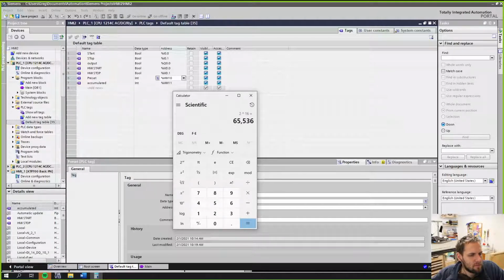Because that doesn't count 0. Right, but this is saying only can go up to 32,000 and only down to negative 32,000, yet this is saying 65. Oh, because it's split in half to have negatives. Excellent. It's split in half, so that way we can go both from negative 32,000 to positive 32,000. So this 65 is actually double whatever the range is, because we can get both positive and negative. So that is a very key point here.